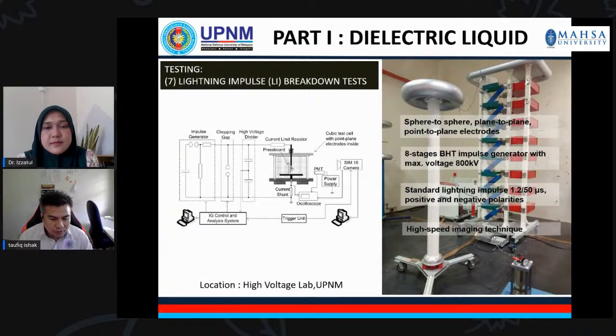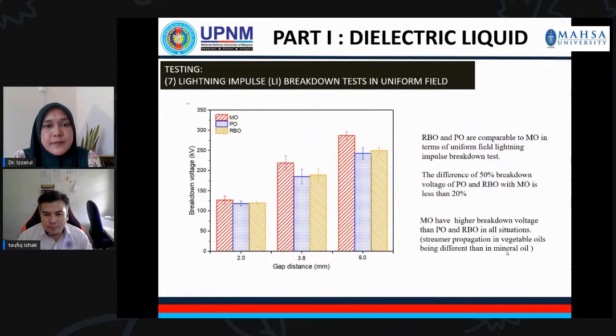Another important study that needs to be done before you can confirm whether this kind of oil can be used inside the transformer is the lightning impulse breakdown test. It is actually to replicate the lightning strike that we have in the real world. The standard lightning impulse that we apply in this study is 1.2 microsecond with 50 microsecond. 1.2 is the rise time and 50 microsecond is the tail time. We have positive and negative polarity, which represent the lightning strike to the earth. Normally the majority of lightning strikes to the earth are of negative polarity.